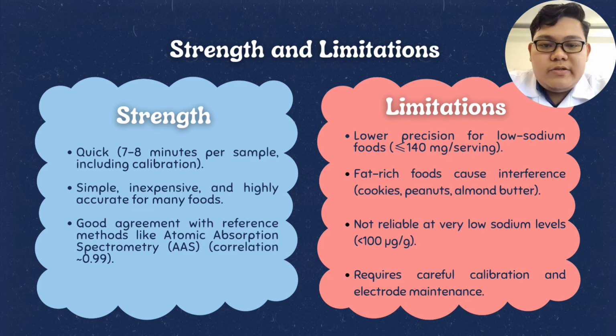Then, for its limitations, it has lower precision for low sodium foods, which is lower than 140 milligrams per serving. Fat rich foods like cookies, peanut, and almond butter also cause interference. And it is not reliable at very low sodium levels, like below 100 micrograms. Lastly, it requires careful calibration and electrode maintenance.